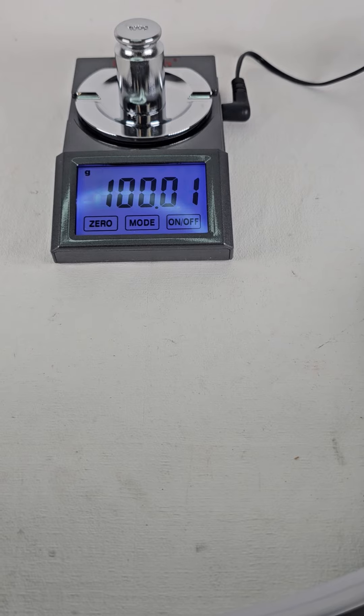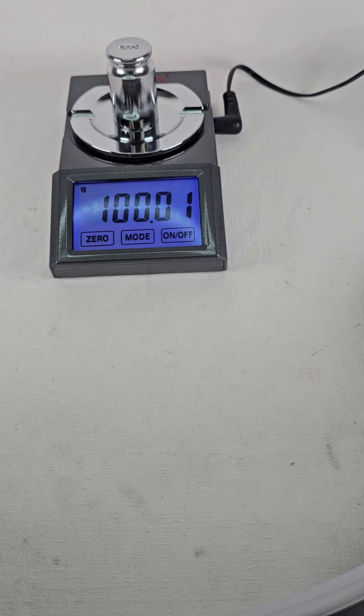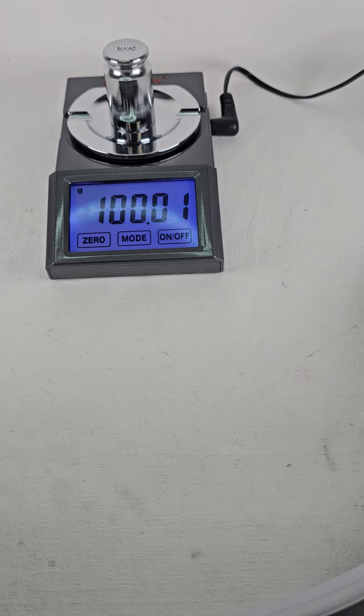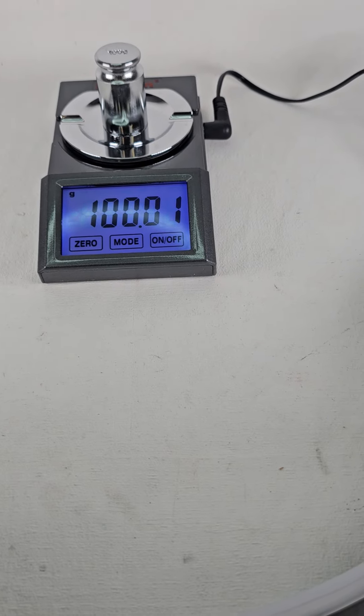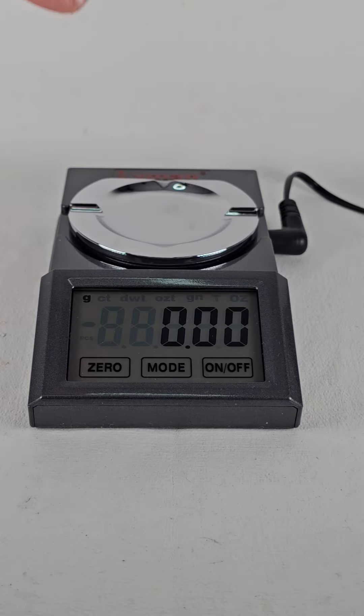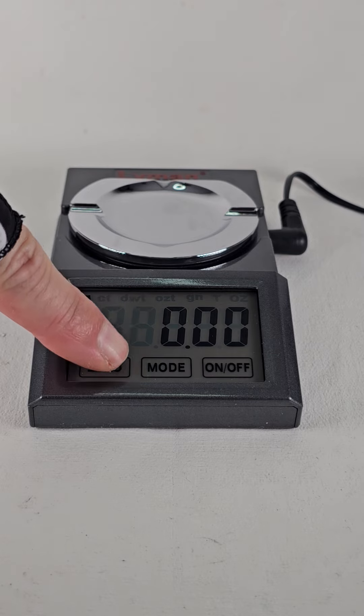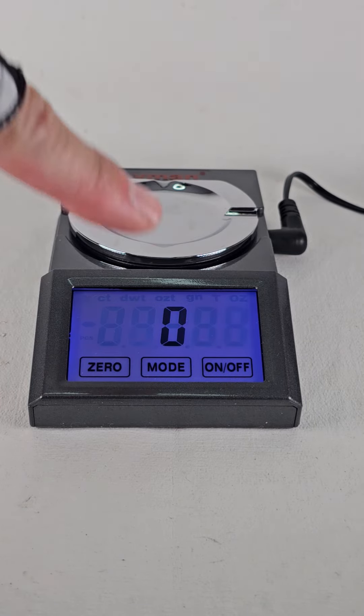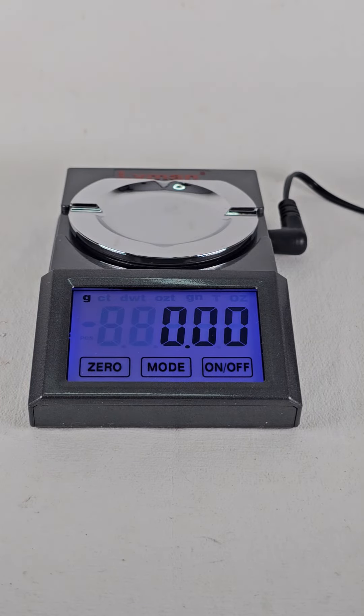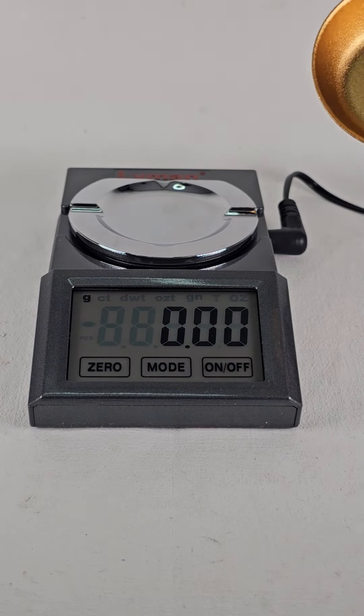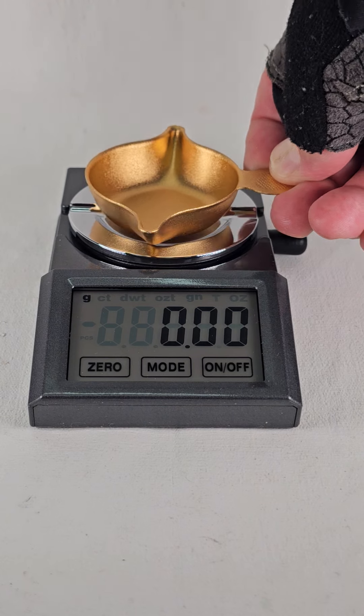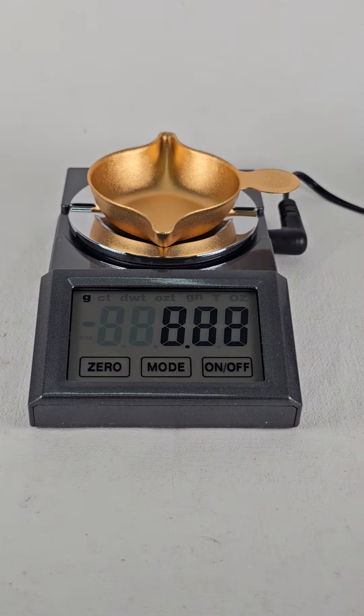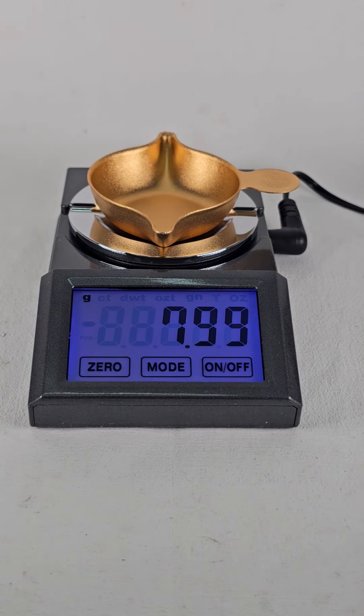Now with the 100 gram weight we've made calibration. You notice the .01. There's typically a variation in weight. The last decimal is expected. Now we're going to zero the scale again and check the tare weight of our pan, which is 7.99 grams.